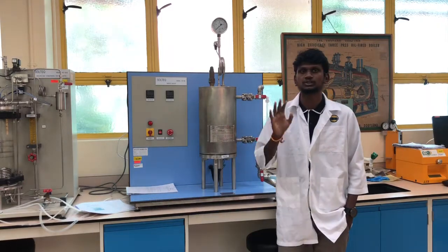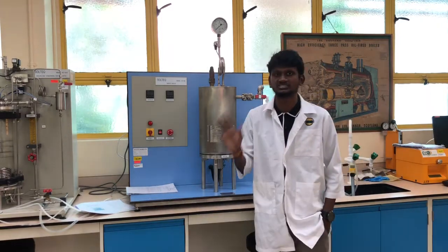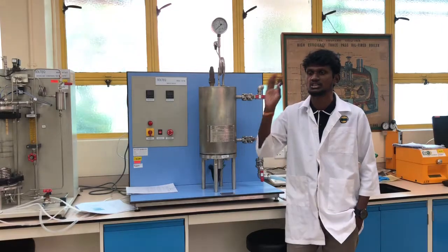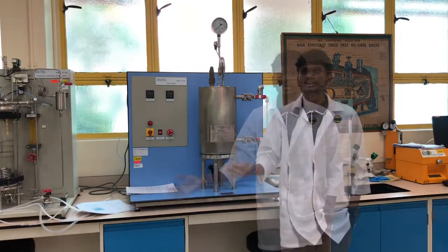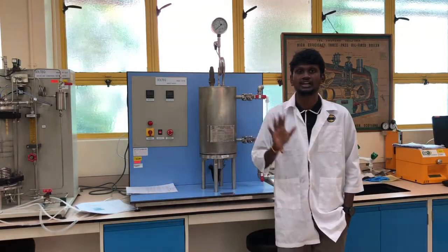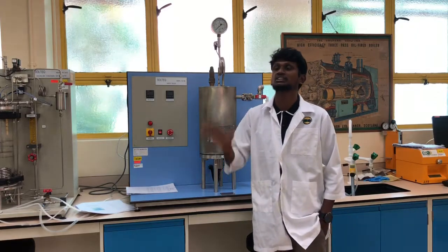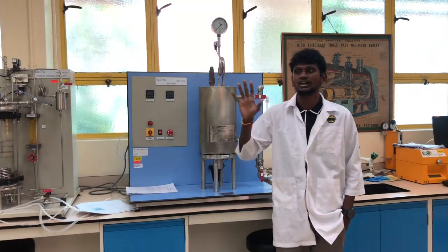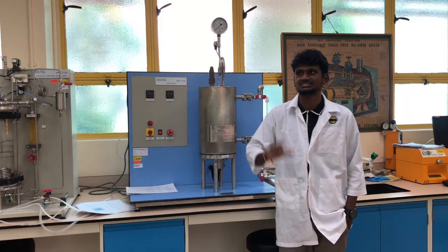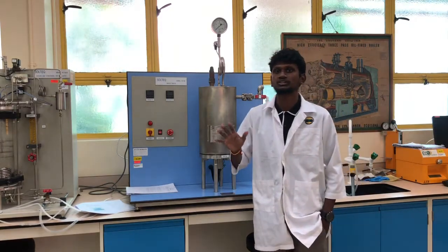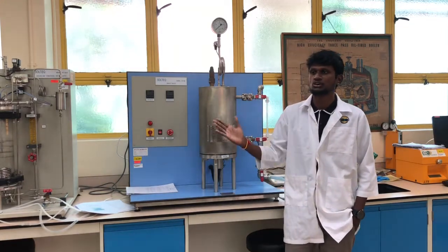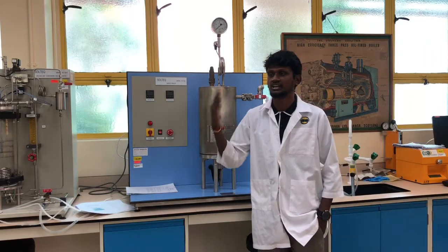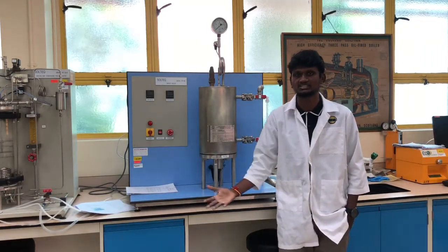The third one is to make sure that the boiler is not restricted by any obstructions such as papers, clothes and so on. And the last but not the least, carry out inspection and maintenance regularly, including its accessories and valves, to check whether the parts or valves are cracked or have any leakages.